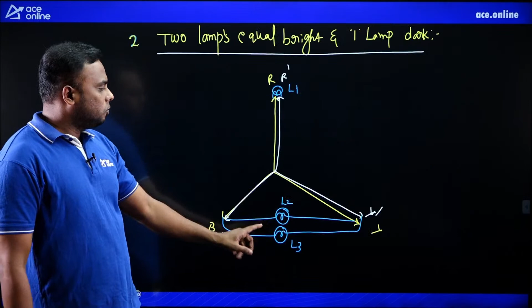So we can achieve the exact in-phase position using this method. That's why we preferred these 2 lamps equal bright and 1 lamp dark. Whenever you get this condition, now you can close alternator to bus bar. So like this we synchronize alternator to bus bar. This is the procedure for synchronization of alternator to bus bar using the lamp method.